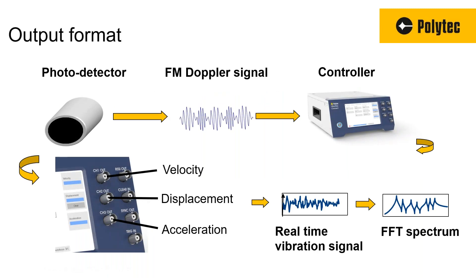What do we get as output? We've always kept the output generic. You could take analog velocity, displacement, or acceleration and take it to your data acquisition system — a simple oscilloscope, FFT analyzer, LabVIEW, whatever you're using. With the new generation of vibrometers, you can also tap into the digital data source directly using an ethernet cable. Basically you get this instantaneous velocity, displacement, or acceleration, and then you do whatever you want with it.